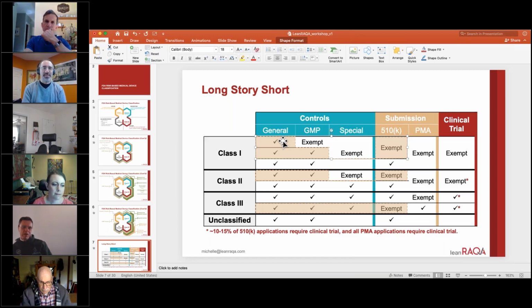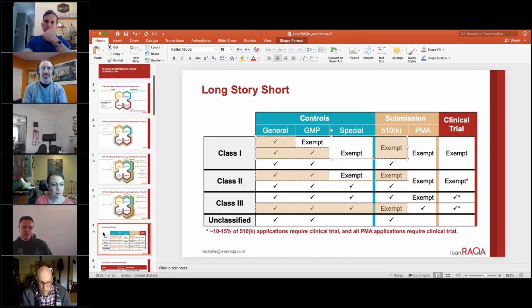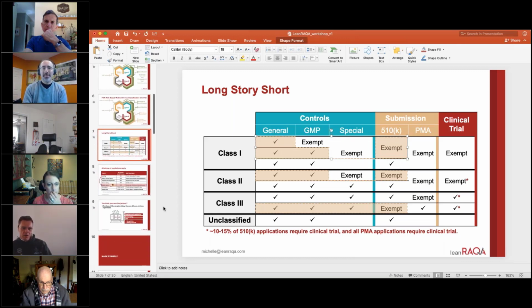Yeah, that's funny. We have about the same thing. We have a 510K approved product, and one of our OEM manufacturers uses it for neurofeedback. And neurofeedback as an application is 510K exempt, but they just want to have it as a marketing thing or so. Right. But if you say you're exempt, but you still say, I want to have a 510K, do you then have to walk the whole mile? Do you have to do everything?